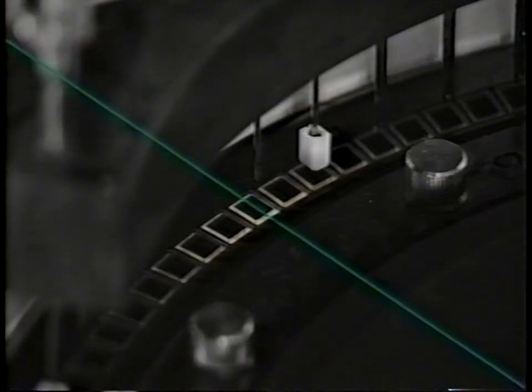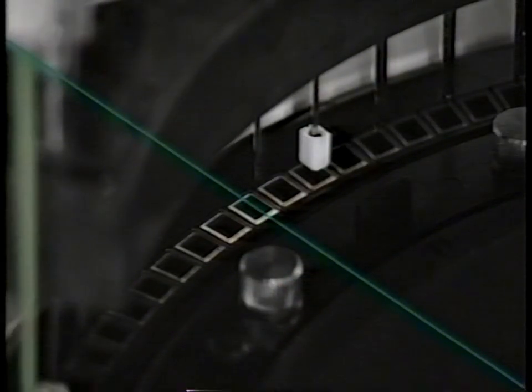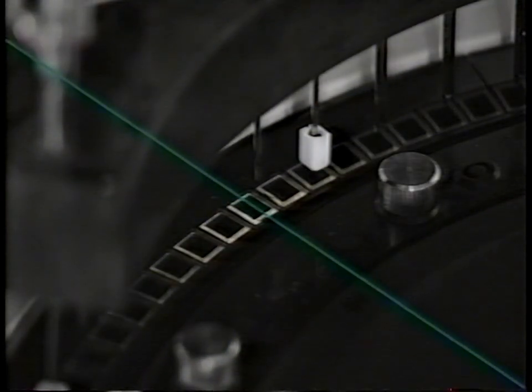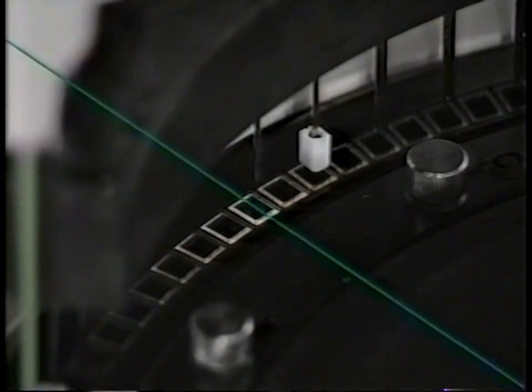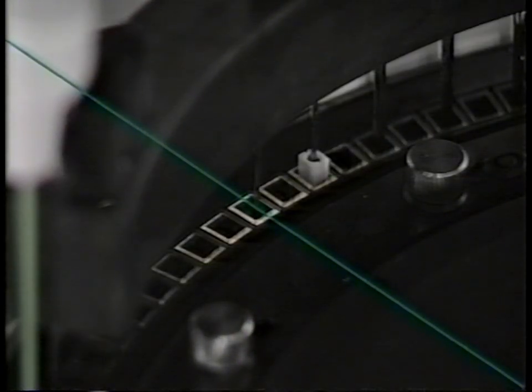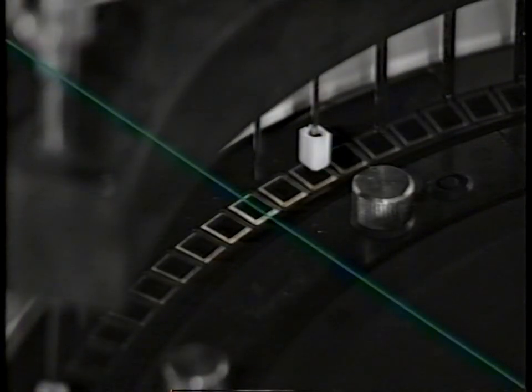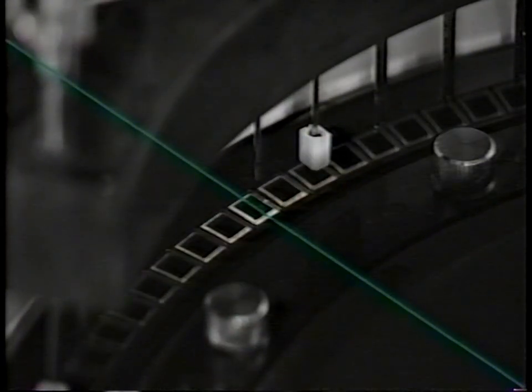The reaction disc turns one full revolution every 20 seconds. Up to 49 readings can be made on each reaction mixture before the cell is cleaned, blanked, dried, and reused for another test. The photometer lamp is located underneath the center of the reaction disc. Its light energy is focused through the cells and into the photometer.